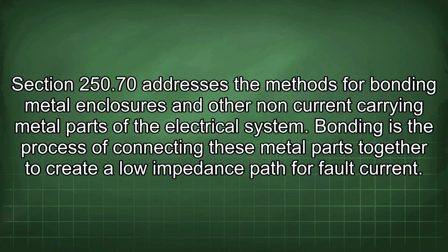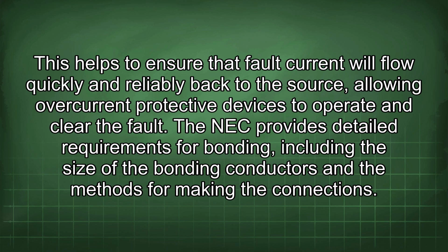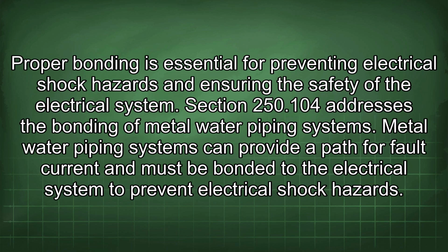Section 250.70 addresses the methods for bonding metal enclosures and other non-current carrying metal parts of the electrical system. Bonding is the process of connecting these metal parts together to create a low impedance path for fault current. This helps to ensure that fault current will flow quickly and reliably back to the source, allowing overcurrent protective devices to operate and clear the fault. The NEC provides detailed requirements for bonding, including the size of the bonding conductors and the methods for making the connections. Proper bonding is essential for preventing electrical shock hazards and ensuring the safety of the electrical system.